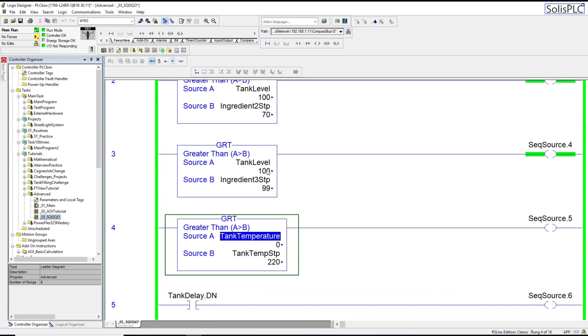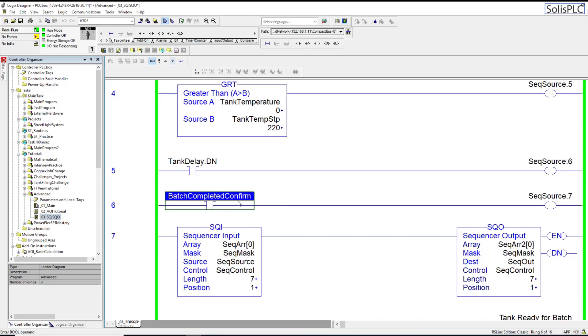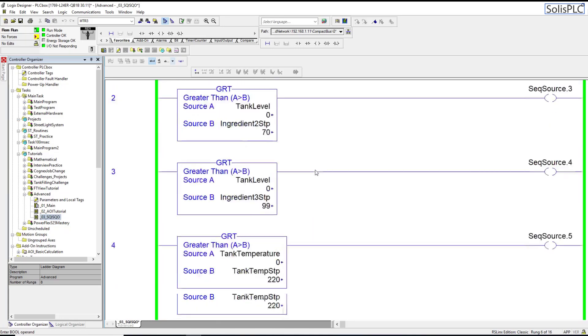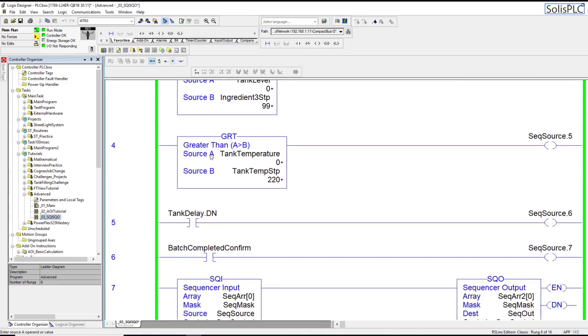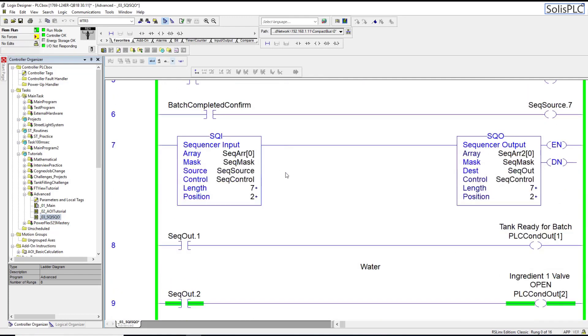The temperature goes back down to zero, the tank level is back down to zero, batch is confirmed, and the position is reset back to one. Think of this as the operator allowing the liquids to go out to a different tank - for example a fermentation process or bottling. The sequence of events has completed. Let's step through the system once again - here we are at the very beginning, the tank is ready for a batch. We start the process with the start push button, we unlatch it because it's a momentary push button, and now we are in step two.